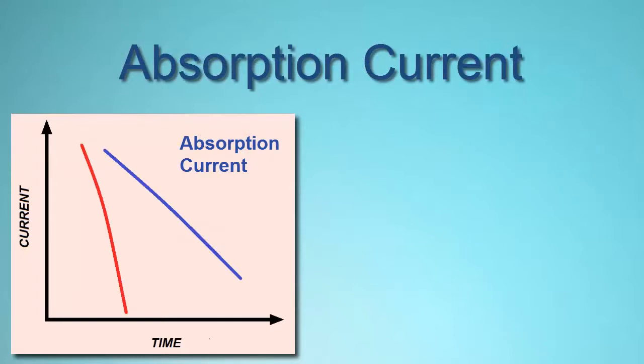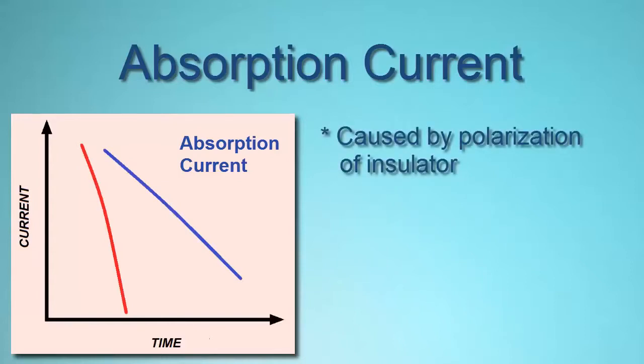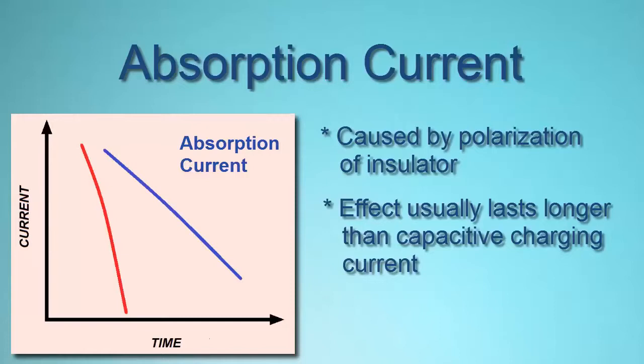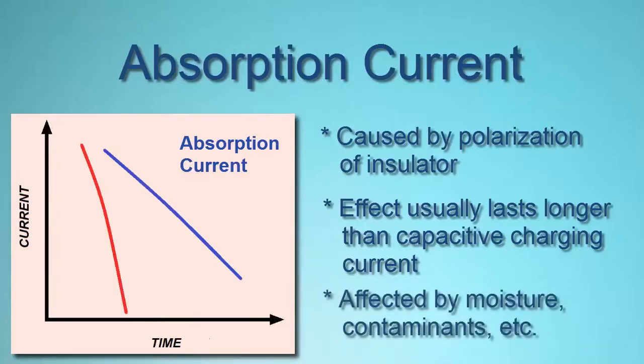Absorption current, also called polarization absorption current, is caused by the insulating material becoming polarized by the electricity flowing through the conductor. As the polarization level increases, the absorption current decreases. This gradual change reflects the storage of potential energy in and along the insulation. As a result, resistance is initially lower and then rises, producing a measurement profile similar to capacitive charging current but at a much lower rate. The effect can last several seconds up to a minute or more. The length of time it takes for absorption current to fall off can be affected by moisture or other contaminants in the insulation material. Therefore, absorption current is an important indicator of insulation integrity.